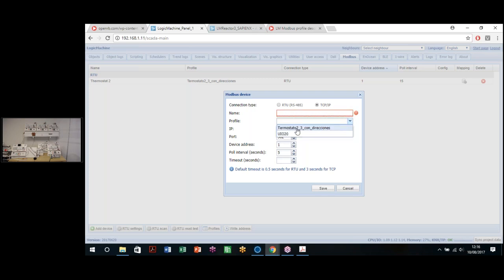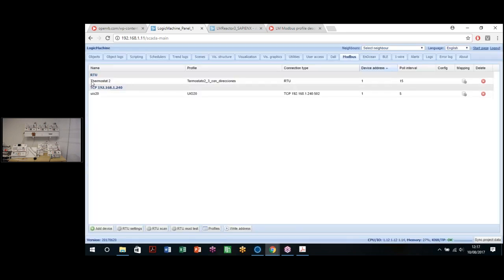The profile works exactly the same as the one we're using for the RTU, so we don't need to create a different type of profile for each device. In this case, let's add a TCP device, even though we don't have one, 192.168.1.240, for example, and let's call it UIO 20, and let's set the IP profile. When we save, it will show that we have a TCP device with this address added. This way we can know which type of communication we have on every device.